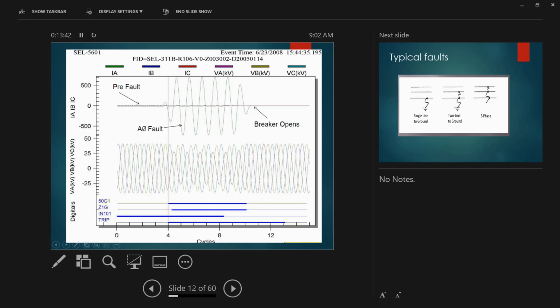So any idea how we can pick this up? How can we feed this huge magnitude to the relay? What is the only way we can pick that up? Yeah, VT, CT. We do CT analyzer, you know. That's why testing the VT, you cannot say it's a simple test, because without the VT, the relay will not work properly. The protection relay is only relying on those parameters that you feed to it.